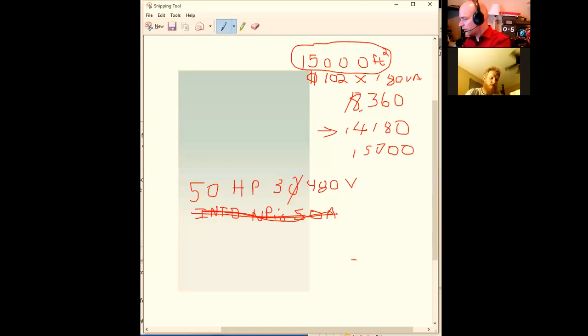5 or 6. So really, the key there is that it's an emergency generator being used for the purposes of emergency support, backup purposes. And it's under 700.12 B6. If it's located inside of the building, then you don't have to have a different disconnect means. But in this case, being outside of the building, you have to have one. B6. Okay, outdoor generator sets.